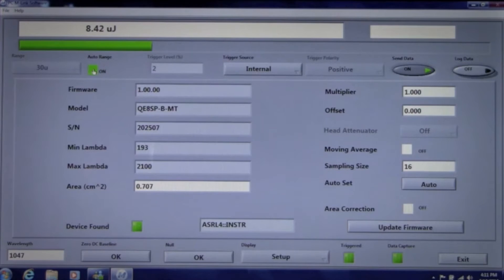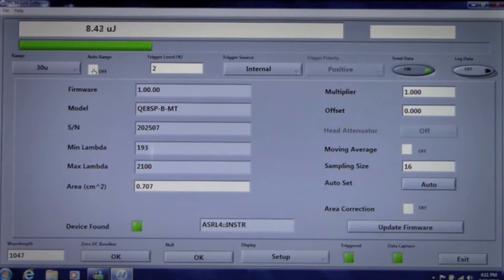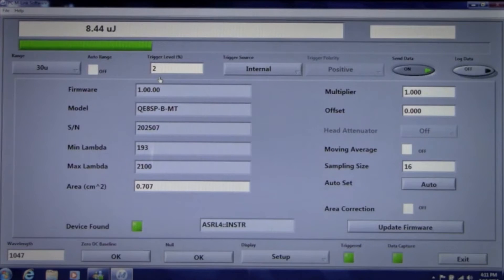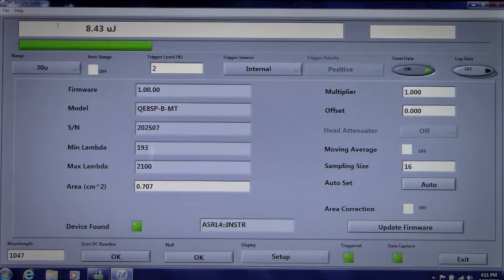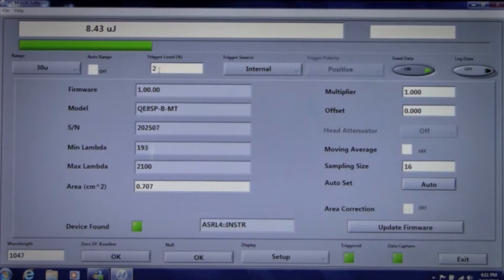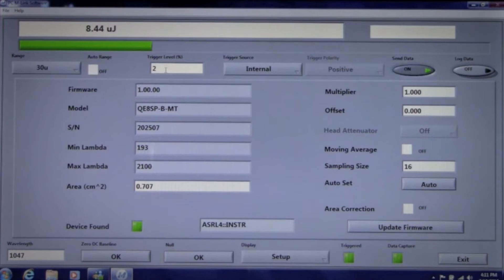I'm going to turn auto range off, but leave the trigger set to internal and the trigger level at 2%. Notice that we display the pulse energy and a green bar graph along with range, trigger, and several other controls. These are always present and available at the top of every screen.